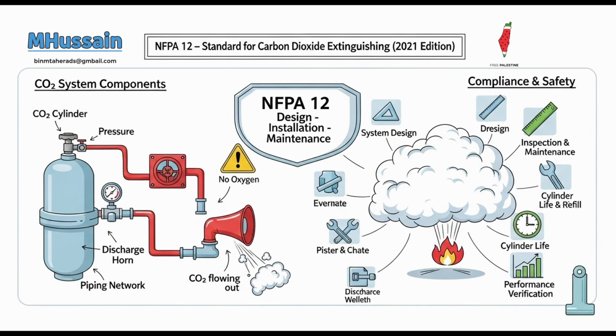Finally, pipe hangers and supports must be designed and installed according to recognized industry practices. You gotta hang the pipes properly. Using steel components attached to rigid structures. They are specifically designed to prevent lateral movement during the high-force discharge. Imagine the sudden kick as a high-pressure gas rushes through, but allow longitudinal movement to accommodate thermal expansion and contraction as the pipes rapidly cool down. Stop sideways movement, allow lengthwise movement for temperature changes? Exactly. Rigid hangers are specifically required wherever there's a change in elevation or direction, providing crucial structural stability. Rigid support at turns and drops.